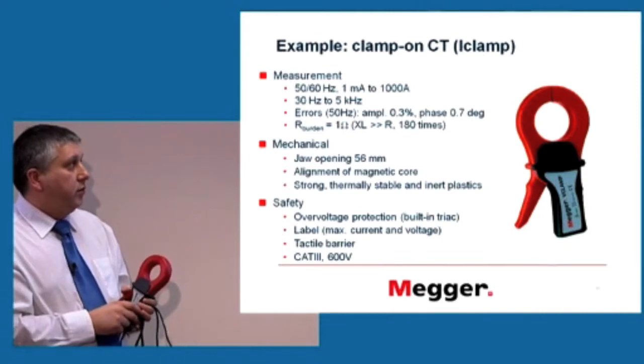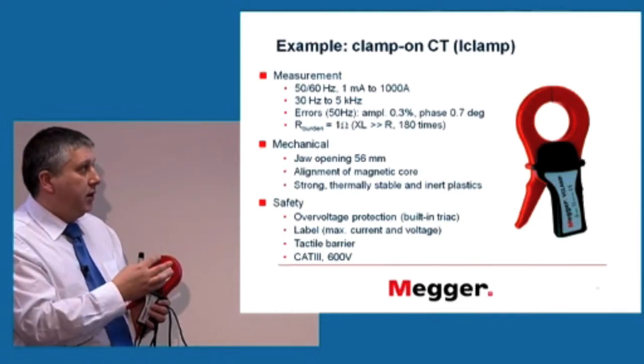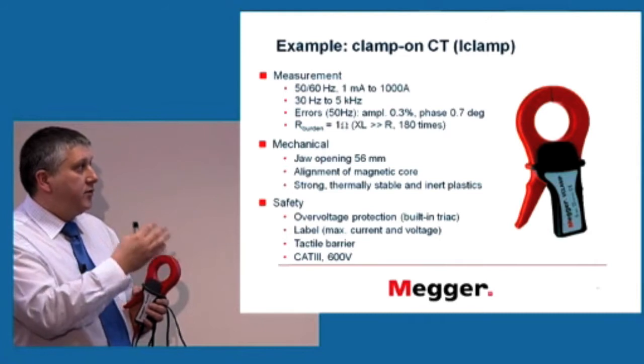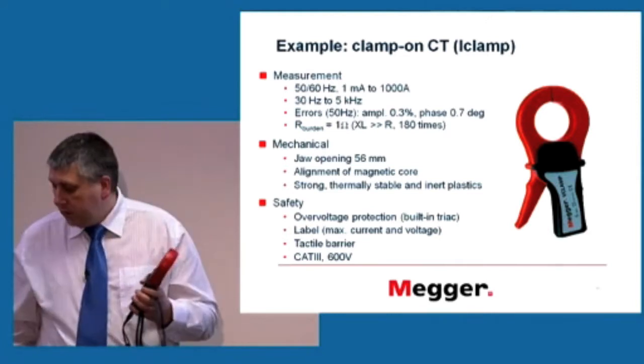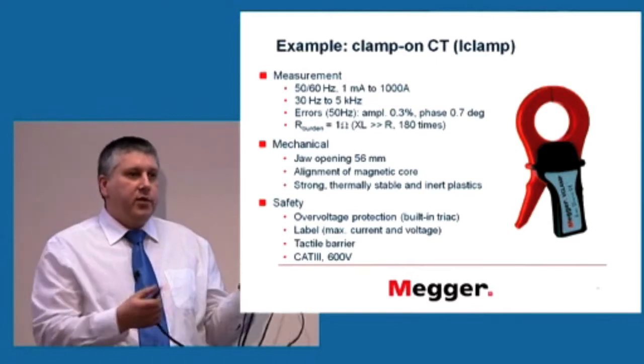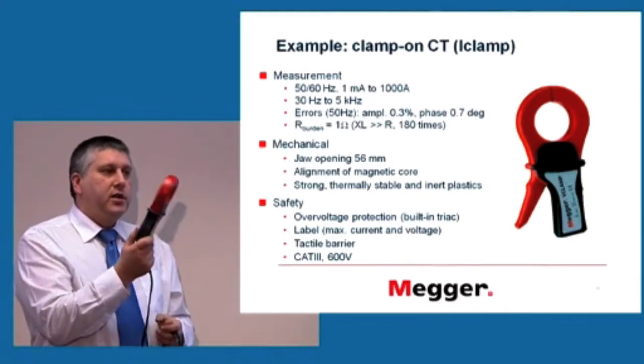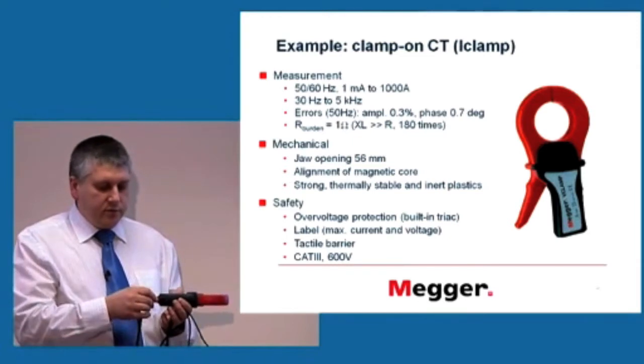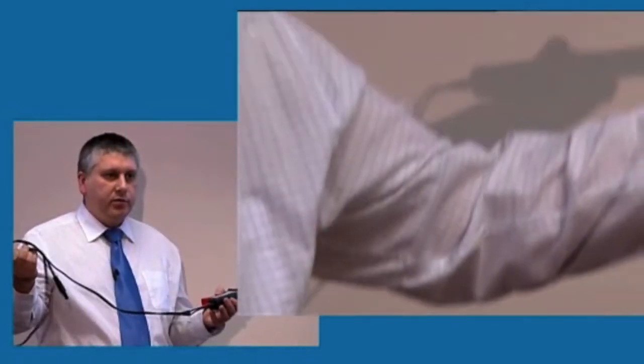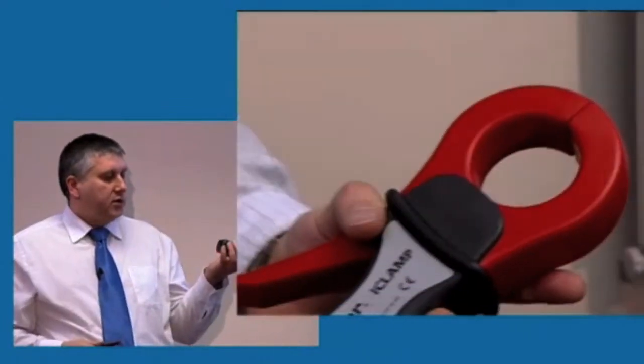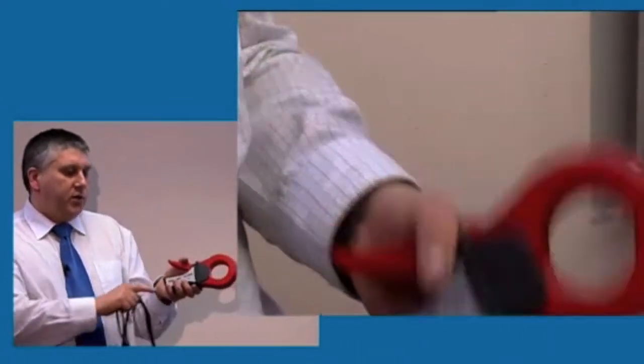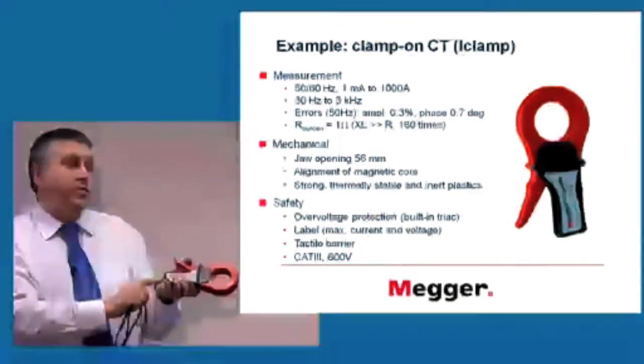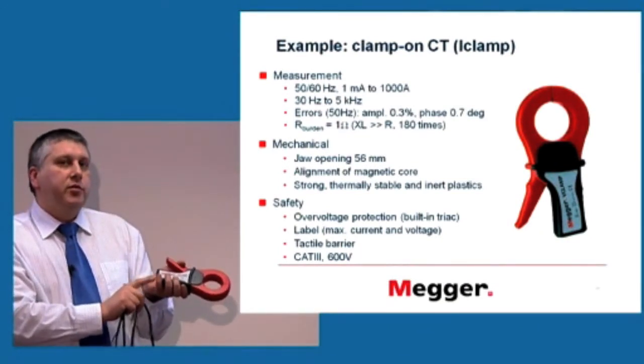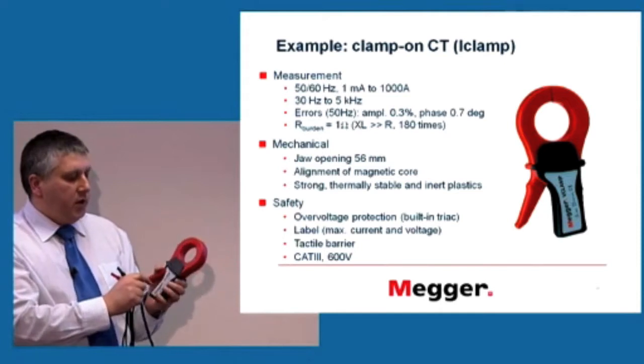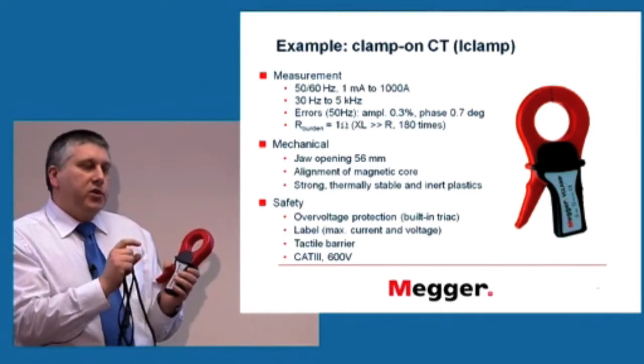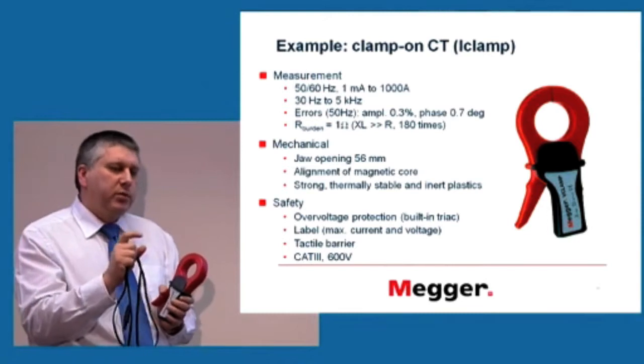And this is exactly what I said related to safety. But there are other things. Over voltage protection, because this is a current transformer which is designed to be connected to something. The burden is not inside the clamp. The burden will be in the device which is connected to that clamp, right? So if there's nothing connected to this clamp and we clamp around something, the transformer circuit is not closed, so very high voltages could be induced. The user has to be protected against that, and this is done by a bit of circuit inside which will basically clamp that voltage to not more than about 24 volts.